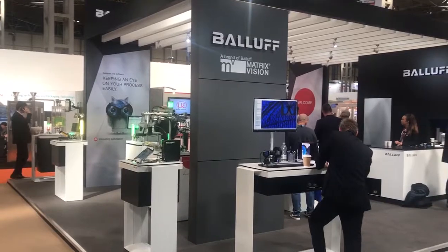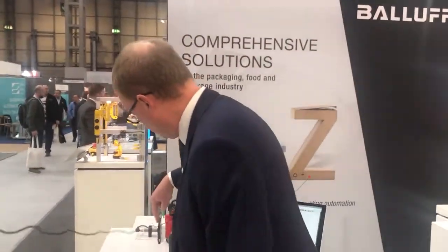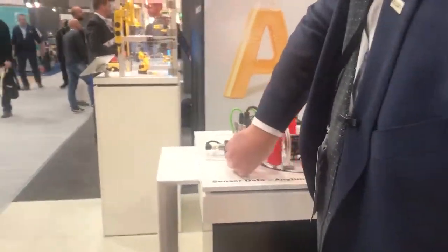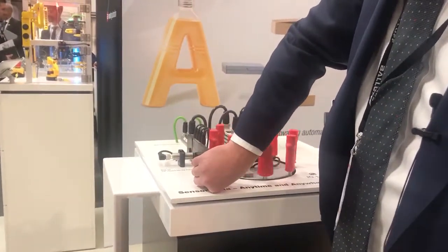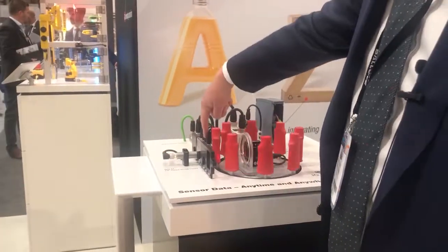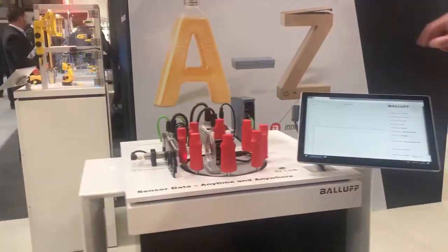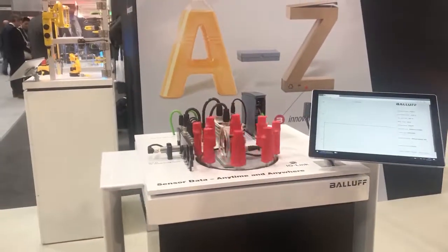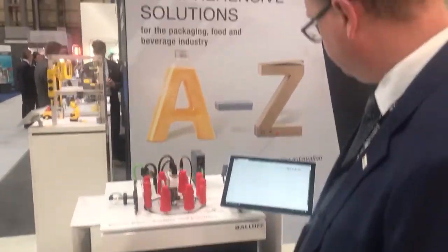So we can set a threshold and send a text message, an email, or sound an alarm to the maintenance team. If I want to change mode, we've got a little RFID sensor on the side, and I change it to the next RFID sensor. You can see it thinking, changing, reads over. This sends a signal down the 3-wire connector to our IO-Link port, to the PLC, back down to the sensor, and it's now changed into background suppression mode. So we can do on-the-fly format changes, and now we're measuring in background suppression mode from the sensor.